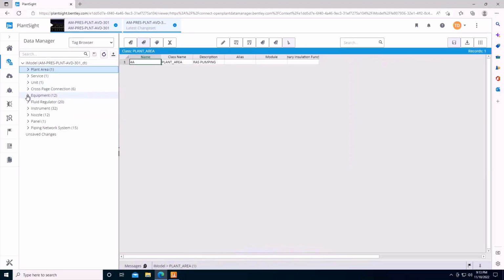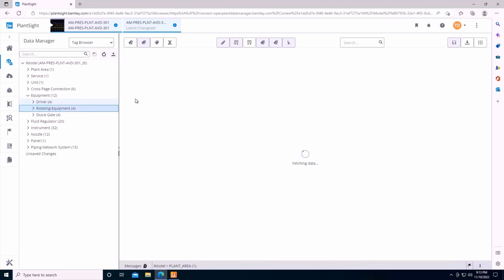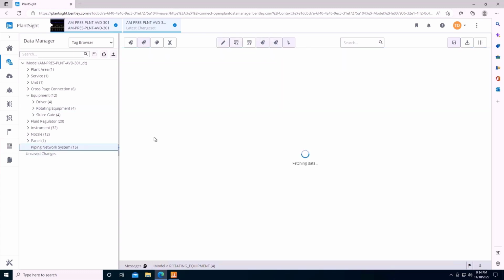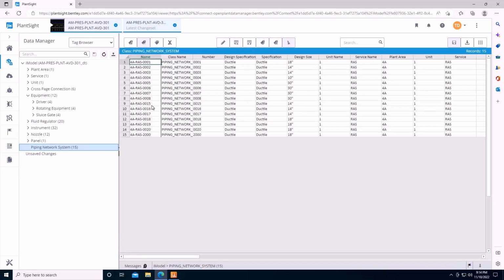After you sync the document to PlantSight, you can see the unique replicated tags created using a query in Engineering Data Manager. This ensures that you can get an accurate bill of materials or component list as required. You can see how tag replication working in concert with virtual instruments can reduce the number of PID documents required and can expedite the overall design process.